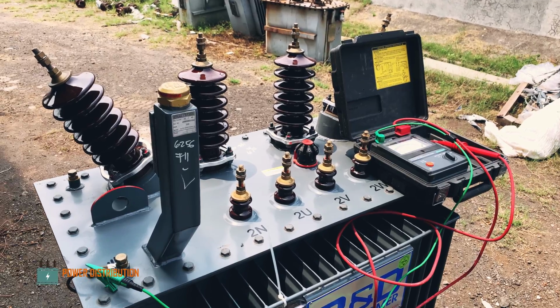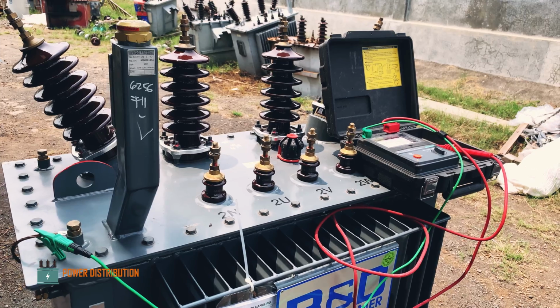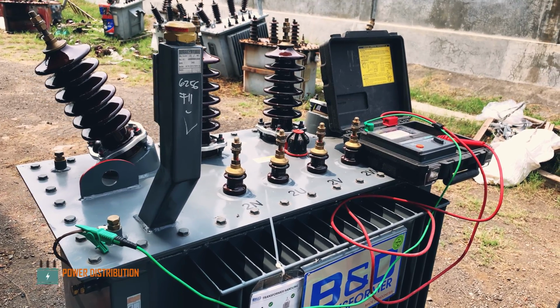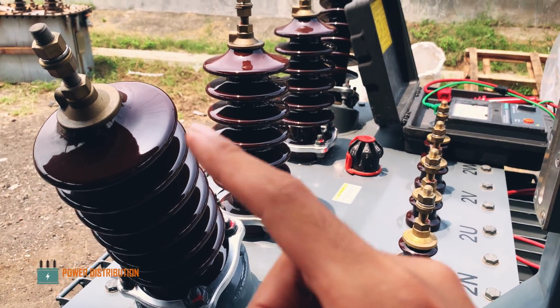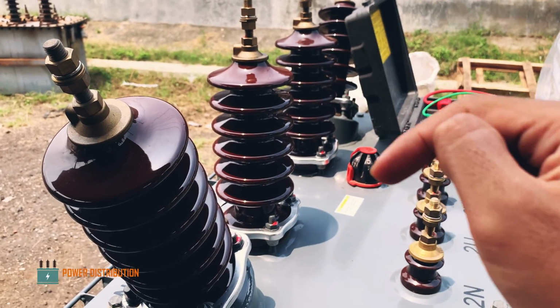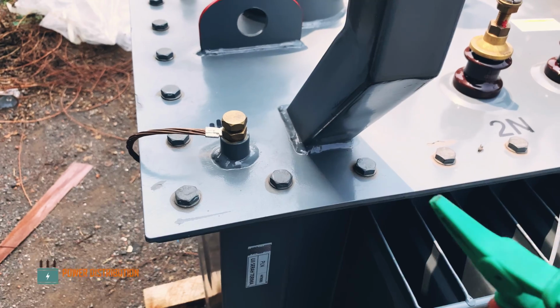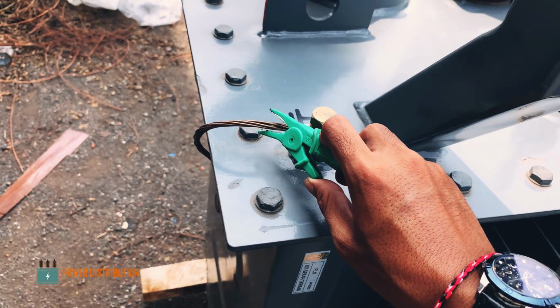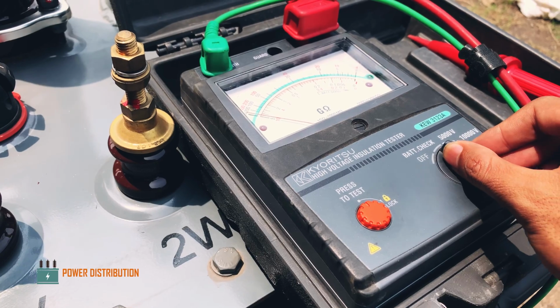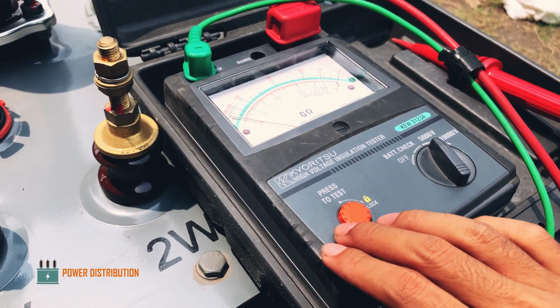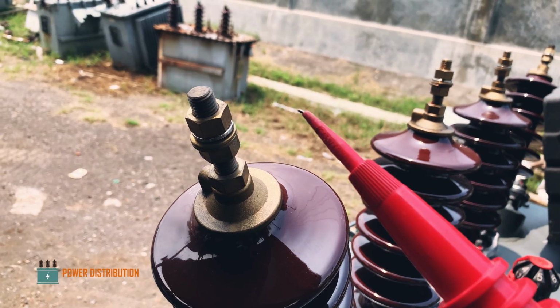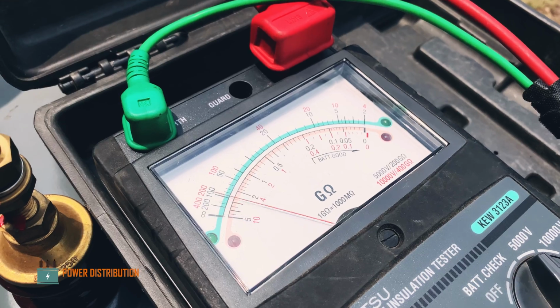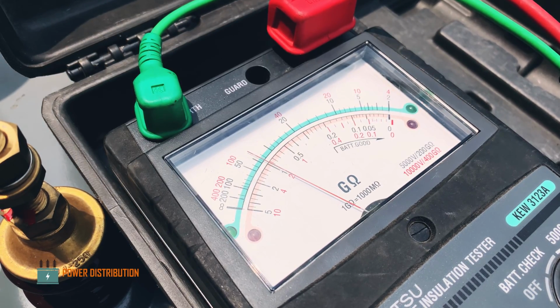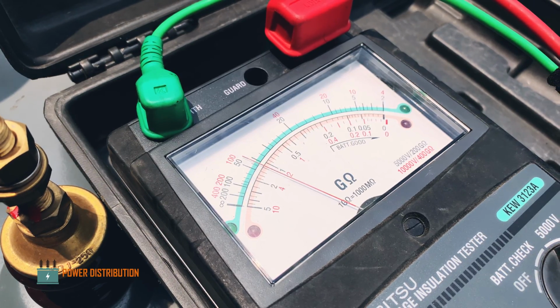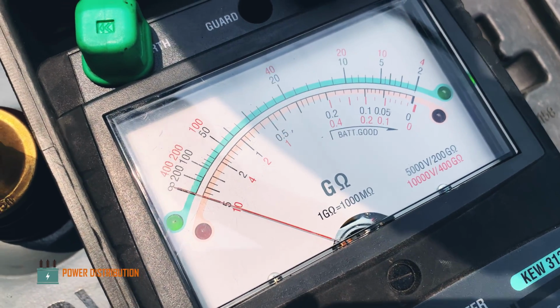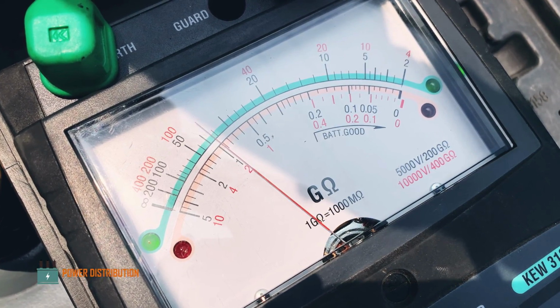I'm gonna use this brand new transformer to demonstrate the process and show you the perfect insulation condition of a transformer. First, we will measure the resistance between the primary bushing or terminal against the ground or the tank. By connecting the earth or the green probe into the ground, set the instrument to 5000 volt and press start. Then touch the terminal carefully, measure it for around 1 minute and read the resistance. The resistance is around 50 gigaohms from the needle, which is very good for this transformer.